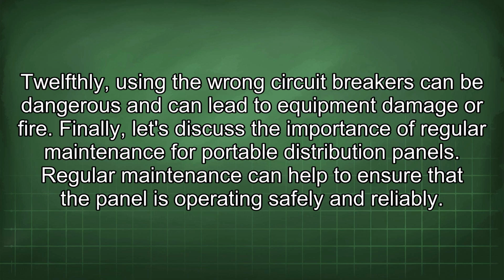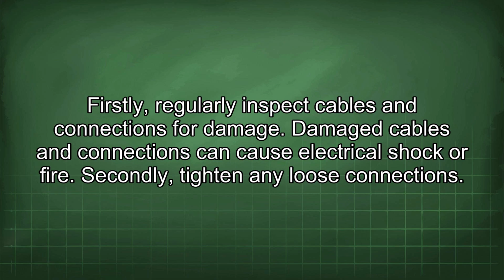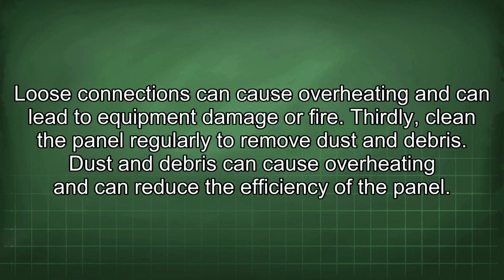Finally, let's discuss the importance of regular maintenance for portable distribution panels. Regular maintenance can help to ensure that the panel is operating safely and reliably. Firstly, regularly inspect cables and connections for damage. Damaged cables and connections can cause electrical shock or fire. Secondly, tighten any loose connections. Loose connections can cause overheating and can lead to equipment damage or fire.